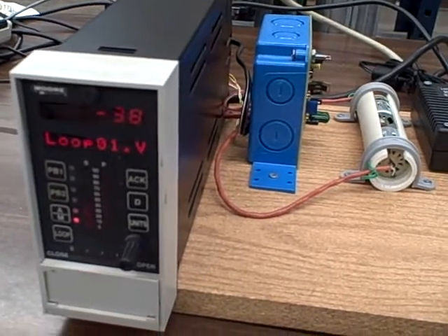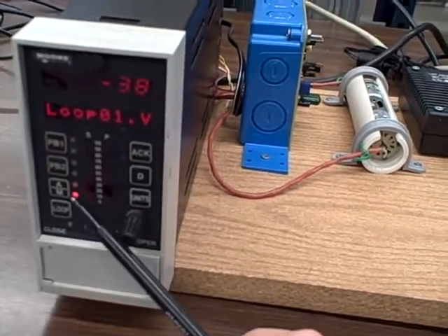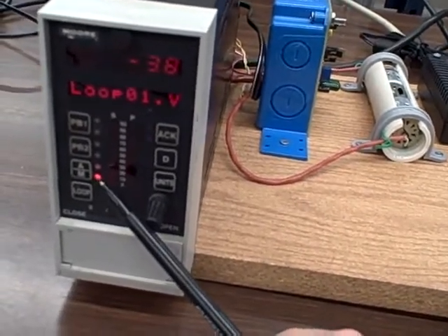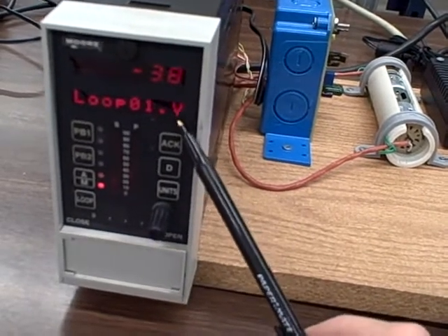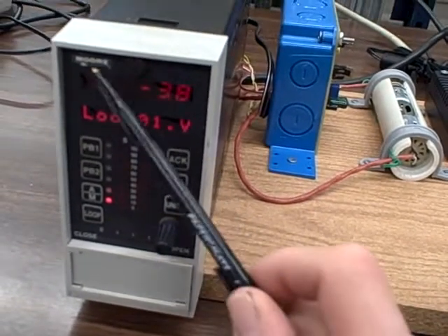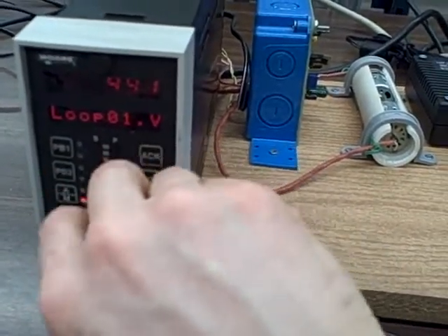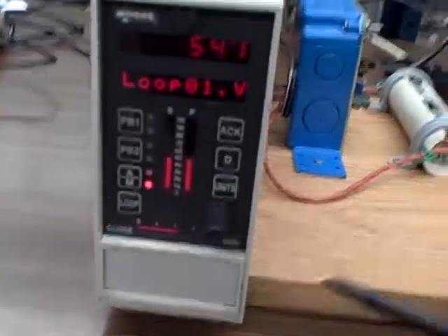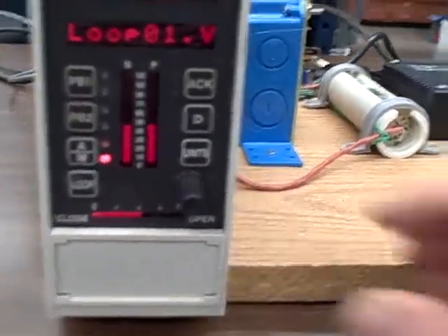First, I'm going to start this up in manual mode. We have the controller set for manual mode, as indicated by the red telltale light. The display says V for valve, which means the output signal in this particular model of controller. I'm going to dial up the output until I get the motor to spin, until we overcome friction. There, we're spinning. And you can see right here in the bar graphs, I'm pretty close to 50%.